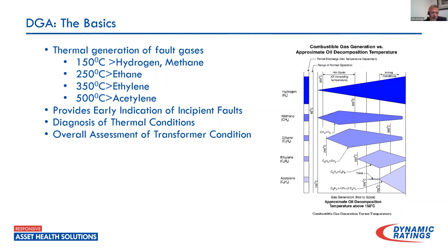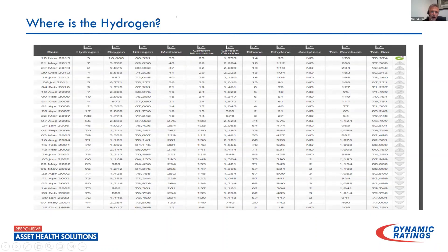Acetylene is often associated with arcing — that's generally the first thing people go to in DGA reports. But acetylene is not necessarily always arcing; it can be a thermal condition, and I have some examples of that. DGA indicators do provide early indication of incipient faults, allow us to do some diagnosis of thermal conditions occurring, and give a good overall assessment of transformer health. This is not the only thing — for true health you'd have to look at LTCs and bushings — but for the core and coil, if I had only a single test I could run on a transformer, DGA would definitely be it.